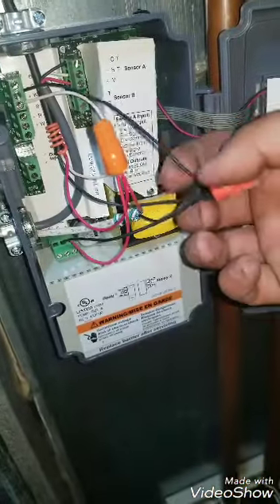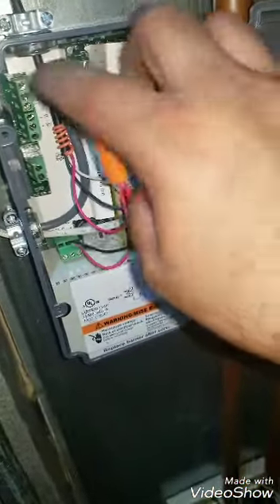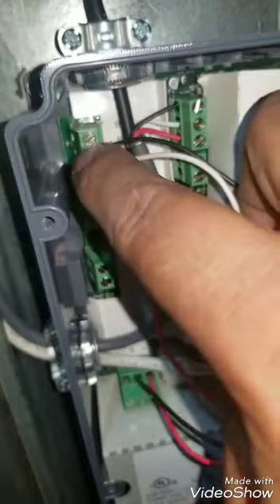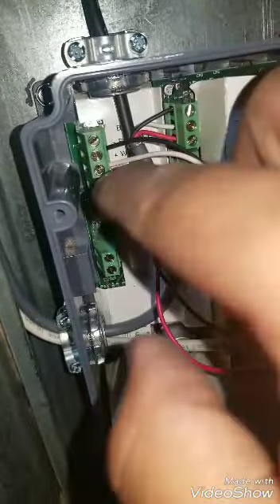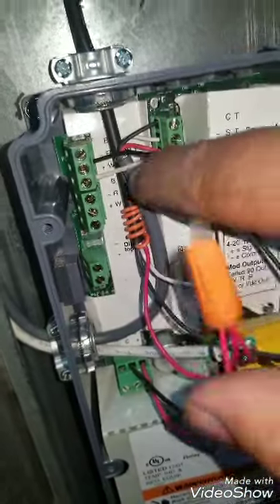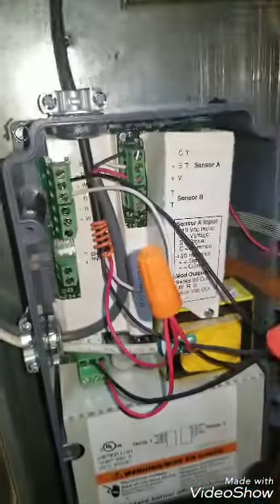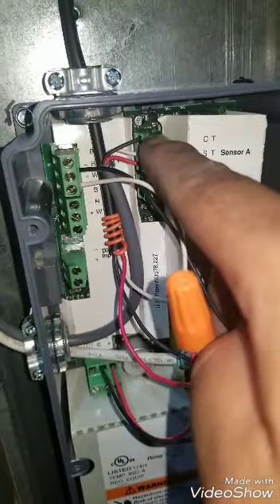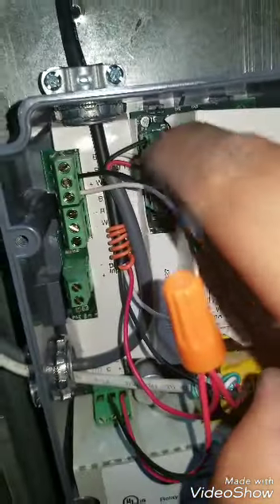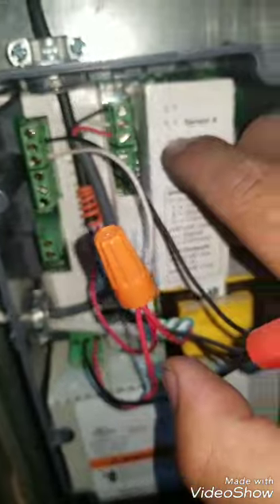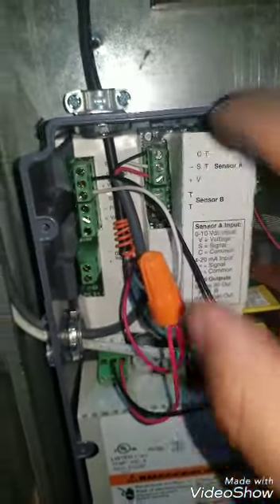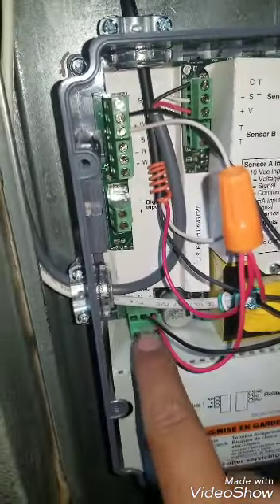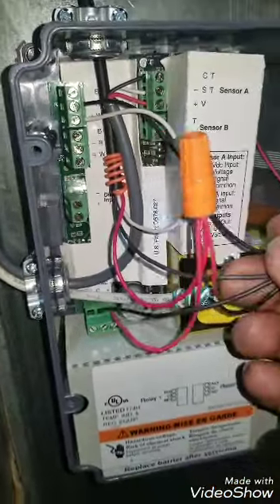This black wire, which is coming from the common side, is gonna be my modulation signal to the damper. Okay? Through the white wire. The white wire goes up into the Belimo. And then these three wires you see back here, black, white, and red, that's coming off the gray wire, which is the sensor. Okay? So the sensor talks here, sensor A. This is the modulation of the Belimo, and then this is the 24 volts. I have the wiring diagram if you need it.